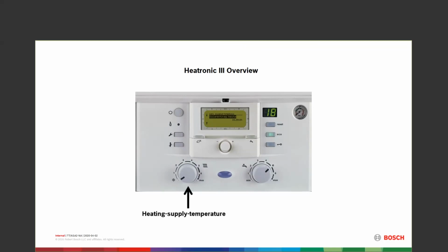We have our heating supply temperature, and that's set on a 0 through max, a 1 through 6. Max being 194, 6 being about 178 degrees. And those are all covered in the manual. They don't set them perfect because each one makes a little bit of a difference. In this way, they didn't have to come up with a temperature from what you're setting it. So just consult the manual if you want to get close. Like I said, max is 194, 6 is about 178. I think 5 is around 160. It goes down from there.